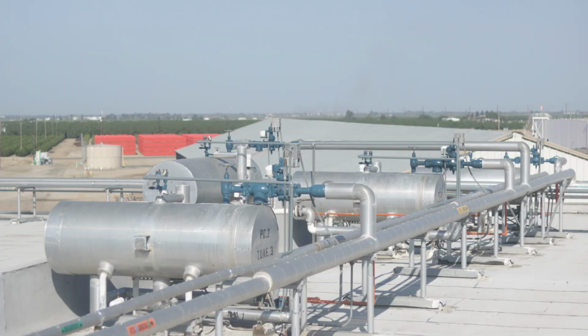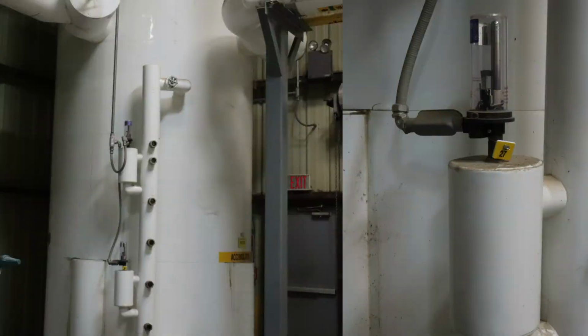Depending on the application of the vessel, specific tests may be required. Vessels that supply vapor directly to a compressor will be configured with a high liquid level float switch that must be tested at least annually for proper operation.